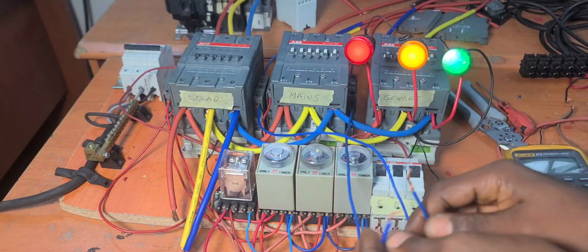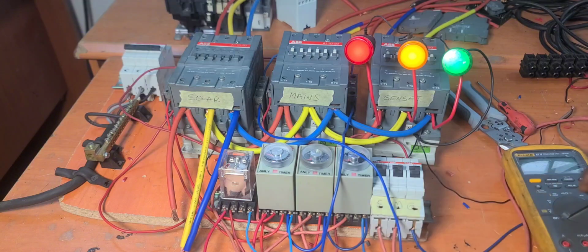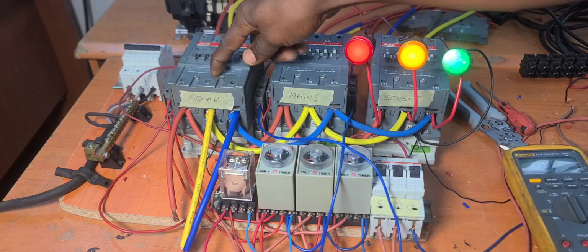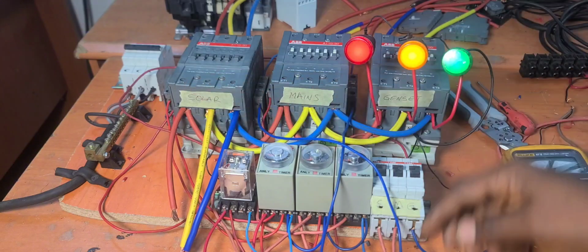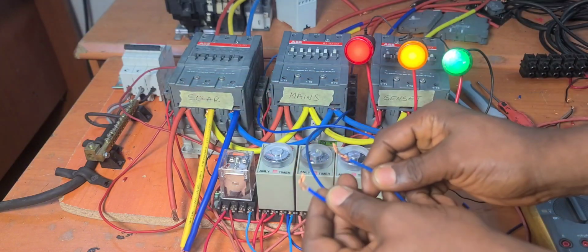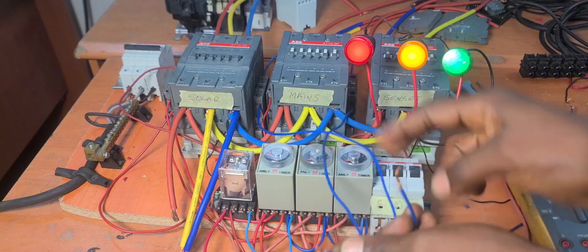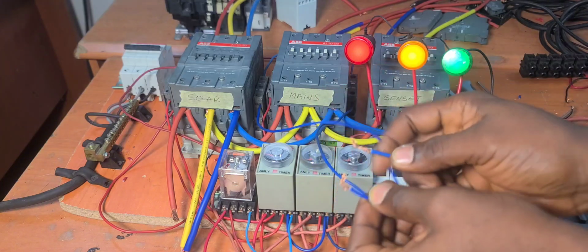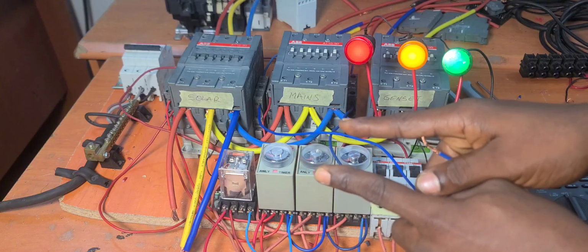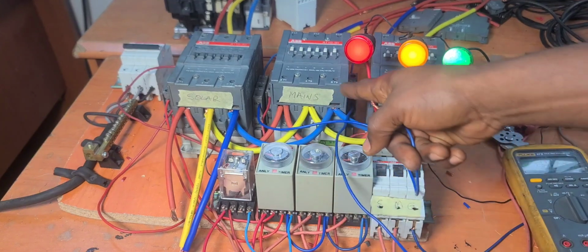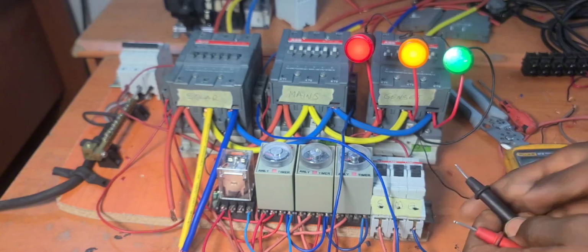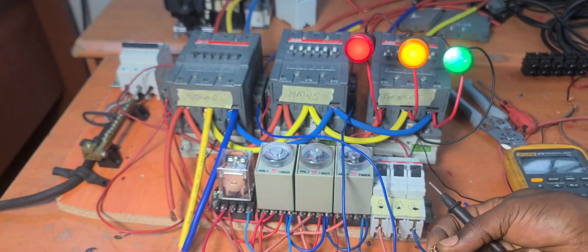All right. Now, what that does is that when solar fails and mains fails, the system is designed to short these two wires. That this is a short circuit internally. What that means is that the two terminals on that controller on the generator is supposed to short. So this system shorts it, and we can confirm that by using our continuity tester to check what happens there.